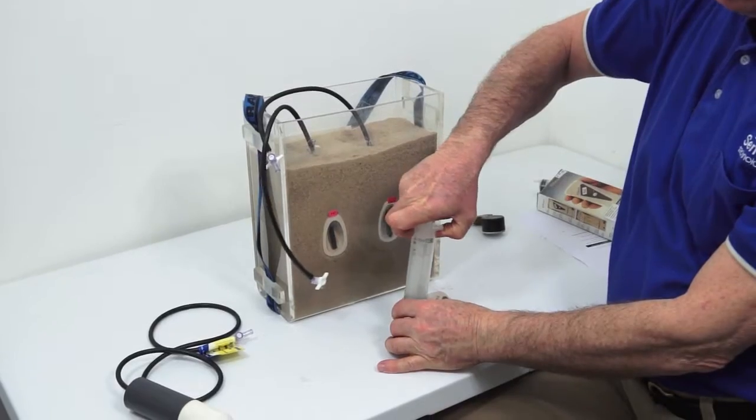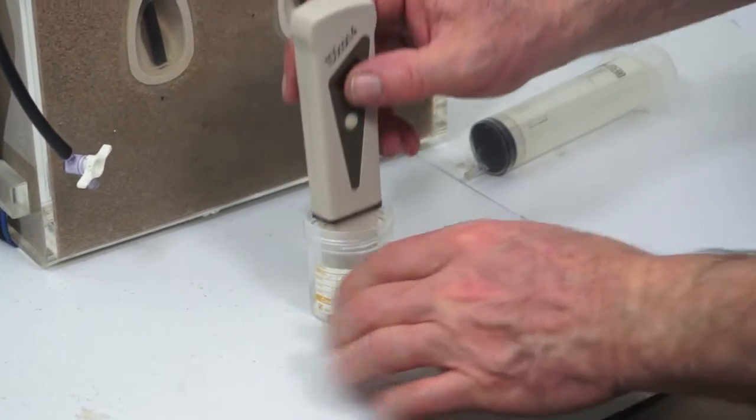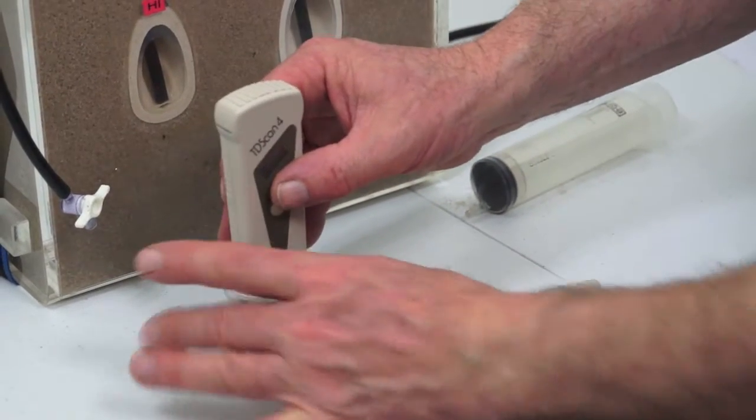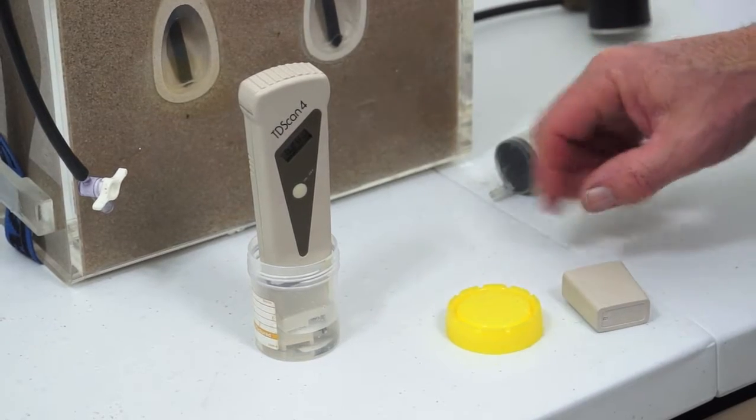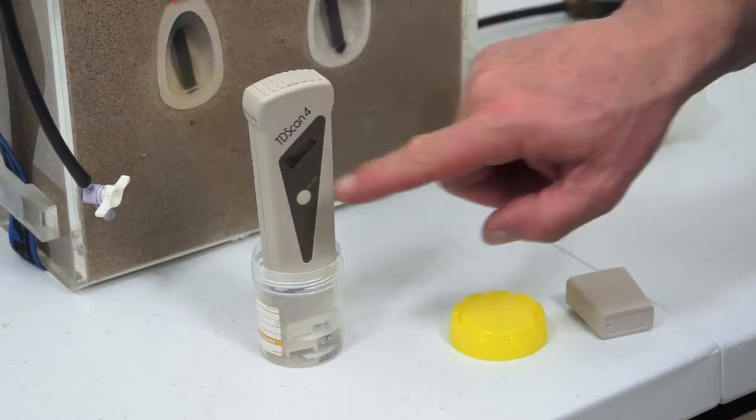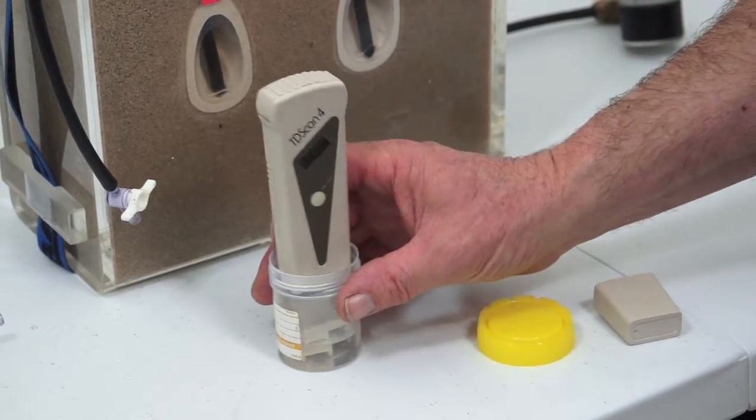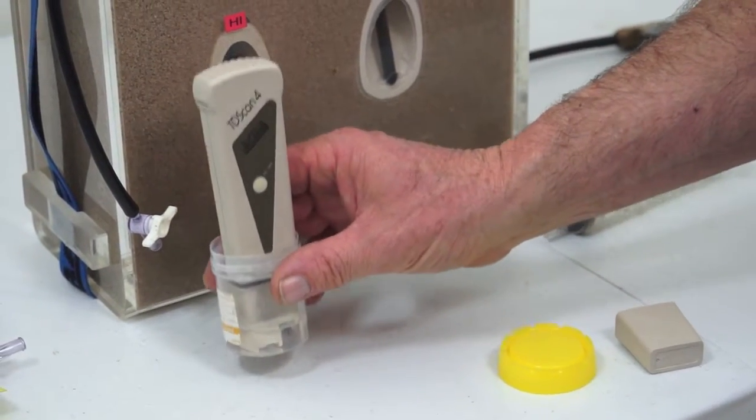We then take our EC meter and we make sure that the solution is covering both electrodes and, if there's one obvious there, a temperature sensor below it. And we wait for the measurement that will be at this scale here to stabilize. This will normally happen pretty fast. And we notice that the measurement at the moment for this solution, which we made up, is 6.2 decisiemens. That's quite a saline solution.